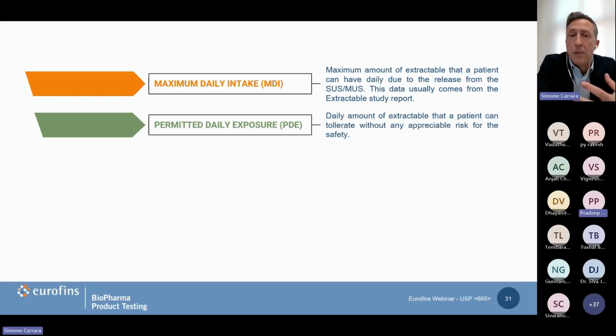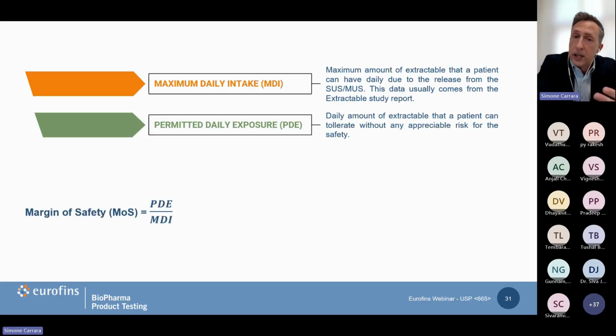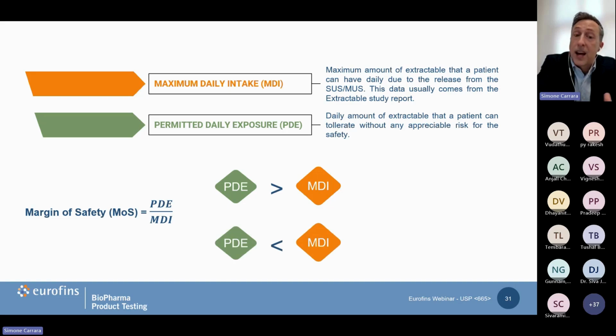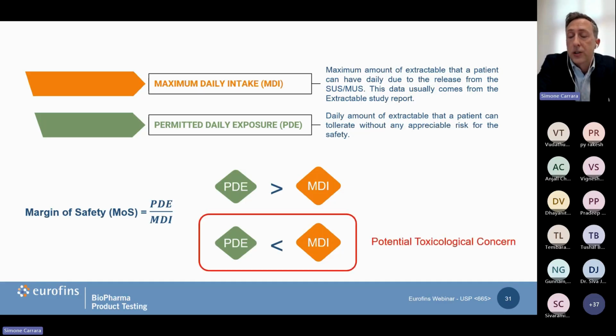So this is the amount that is coming from the extractable study, the amount that you can see in the table of that study. Permitted daily exposure instead is the daily amount of that extractable that a patient can tolerate per day. So if we put in ratio these two parameters, we obtain what we call the margin of safety. In the case the PDE is higher than the MDI, we are on the safe side. In the case the MDI instead is higher, so the amount that I found in the extractable study is higher than the amount that I can tolerate daily, of course, I can have a potential toxicological concern.